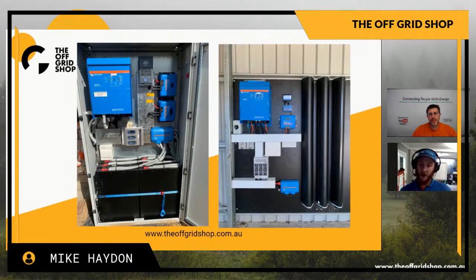This customer would be able, if they pulled the full 8 kilowatts out at once, to trip these circuit breakers. But the reality is, right now it's in a shed with not much going on in there. So it's obviously a lot - the best thing to do is put the biggest inverter possible up to start off with, because you can always add the batteries.